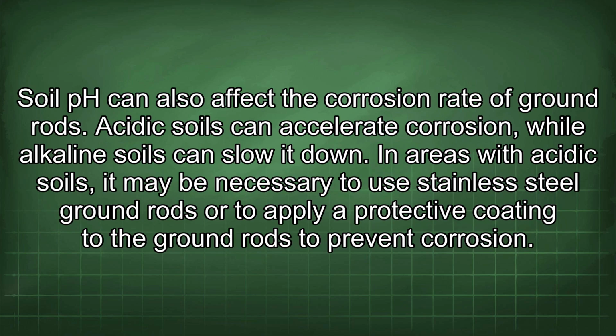Soil pH can also affect the corrosion rate of ground rods. Acidic soils can accelerate corrosion, while alkaline soils can slow it down. In areas with acidic soils, it may be necessary to use stainless steel ground rods or to apply a protective coating to the ground rods to prevent corrosion.